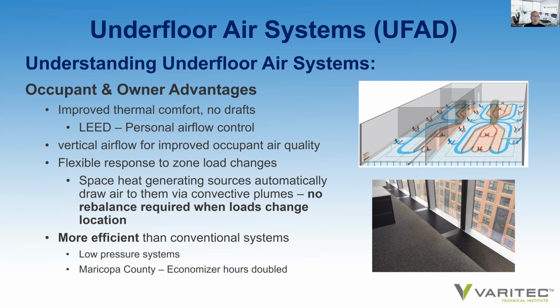Plenum pressures are designed at 0.05 to 0.08 inches, possibly 0.1 inches of pressure, a significant reduction in fan energy. And also in Arizona, where we are dry in our shoulder seasons, fall and spring, we can actually double economizer hours because air supplied by underfloor air systems is not at 55 degrees, it's at 65 degrees to prevent thermal comfort issues of overcooling feet and ankles.